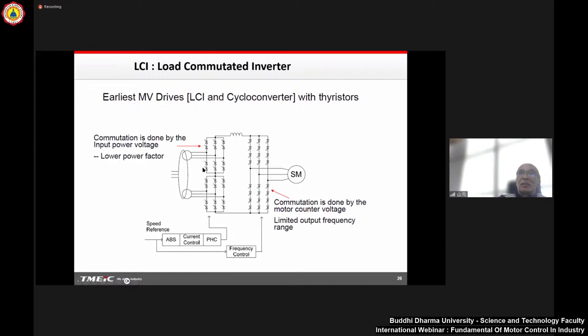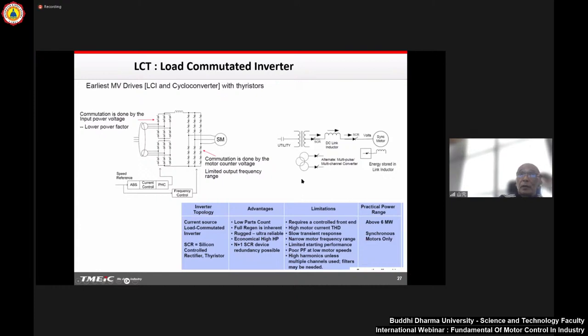What happens here is the input side power factor is zero, because there is only current flow but no DC voltage. So with this configuration, we need to consider the poor power factor operation on the power supply side, which is one of the big disadvantages of current source drives or LCI. This is shown here as the input level power factor.